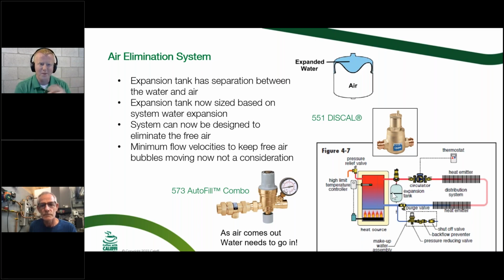But it was brought up to my attention that you get an air separator in that big wide passageway there, that low velocity zone. It actually acts a little bit like a dirt removal device too. And despite the fact that the air separator is shallow, it could still get a little bit of dirt and debris inside those expansion tanks. So just something to think about, instead of putting that expansion tank here, on a low pressure drop type boiler, you could actually take that expansion tank and put it right here, connect it with your fill valve right over here, and it's not going to make that much of a difference.